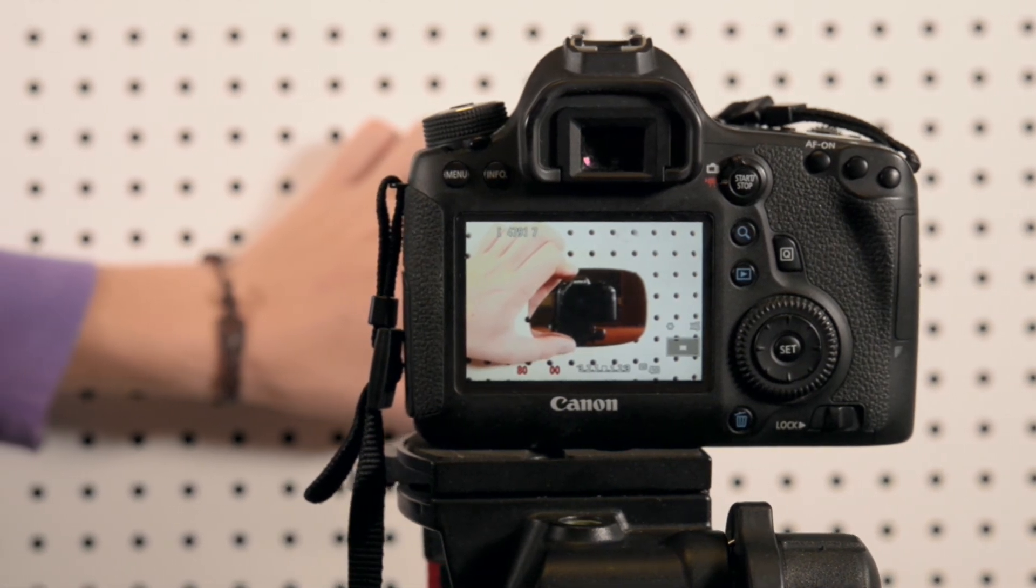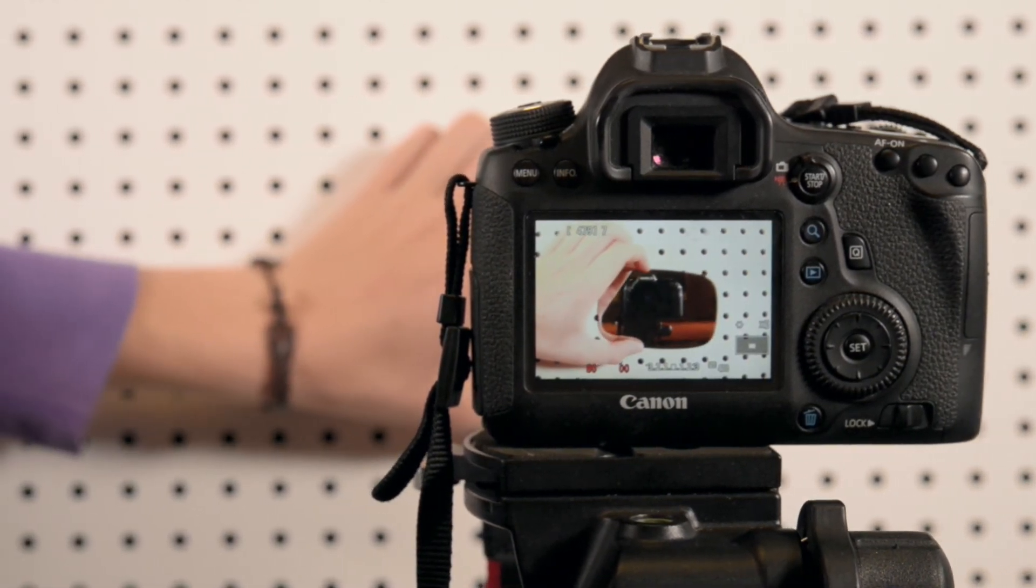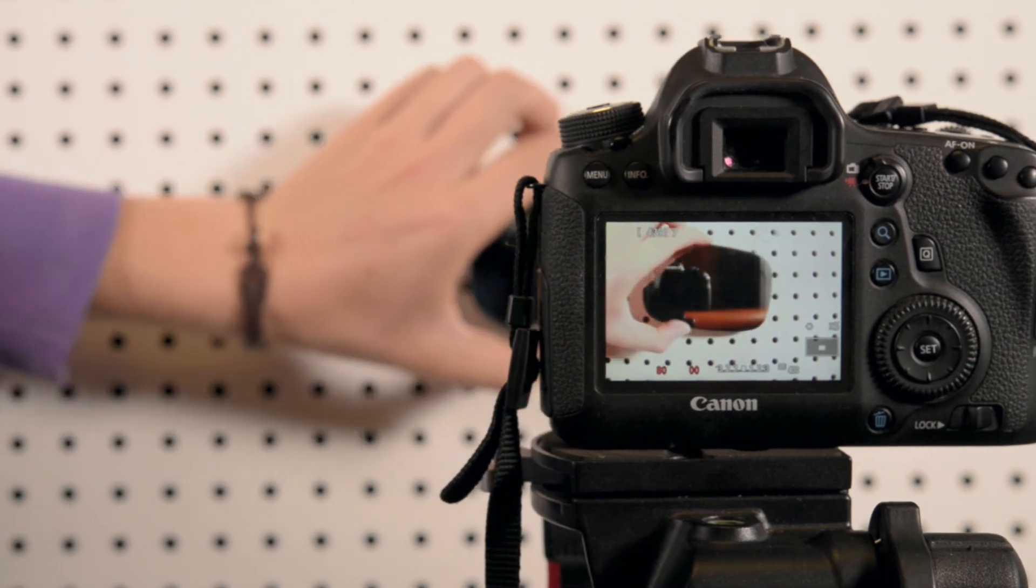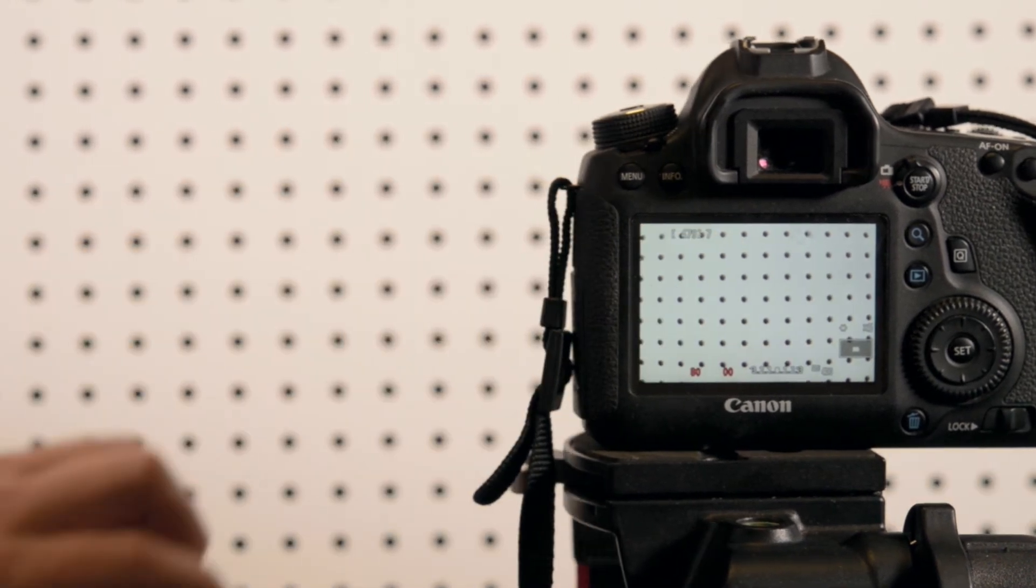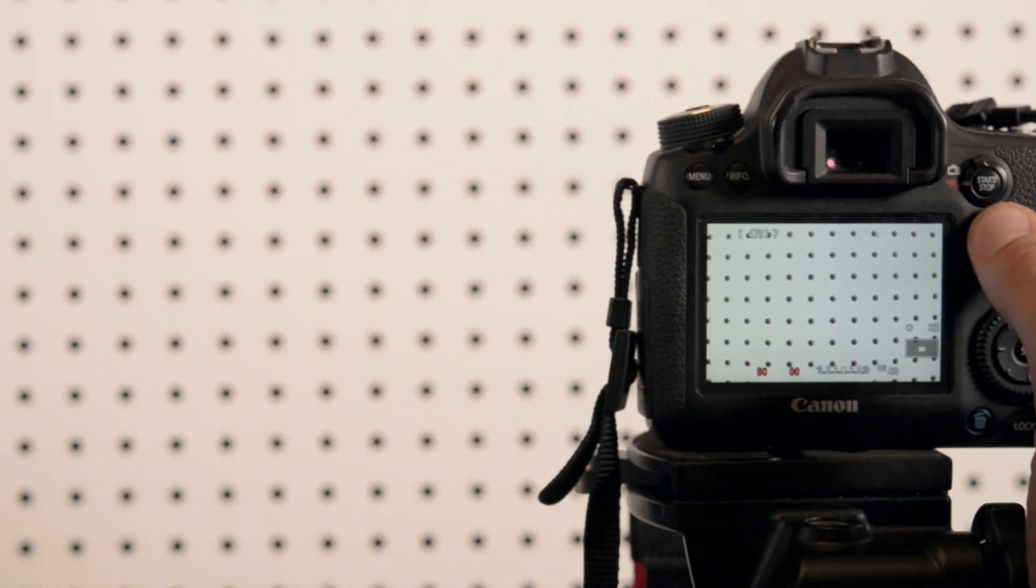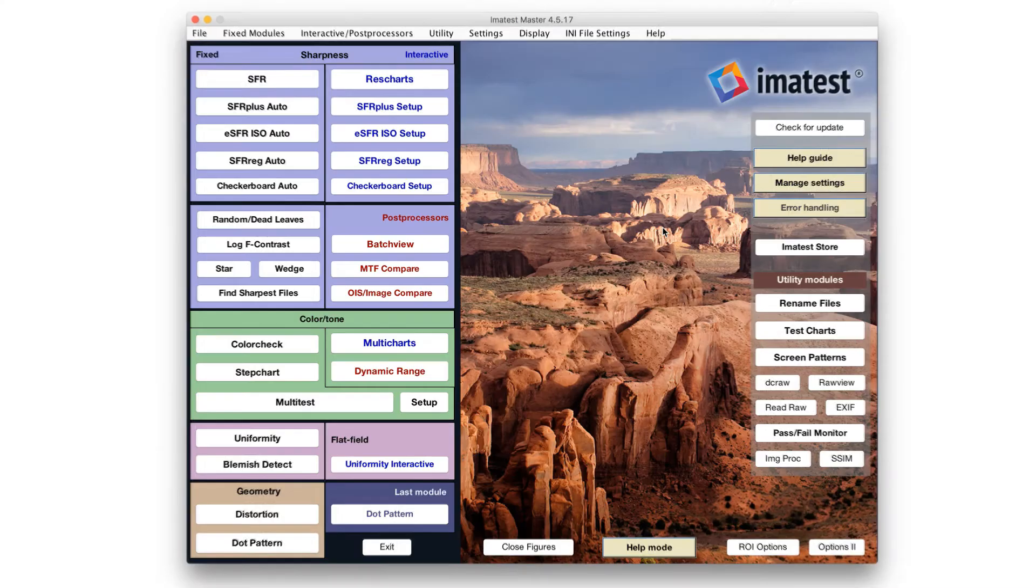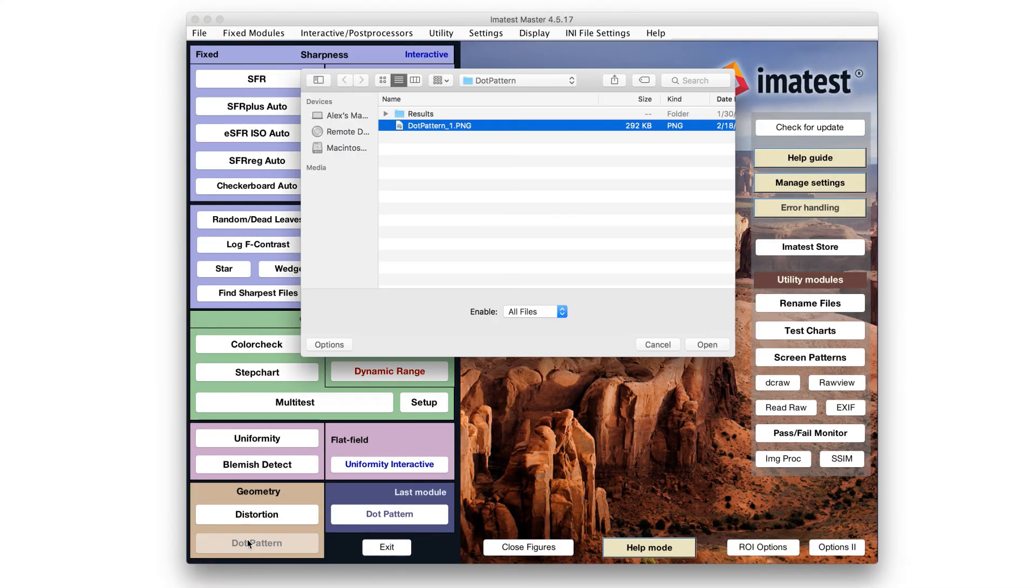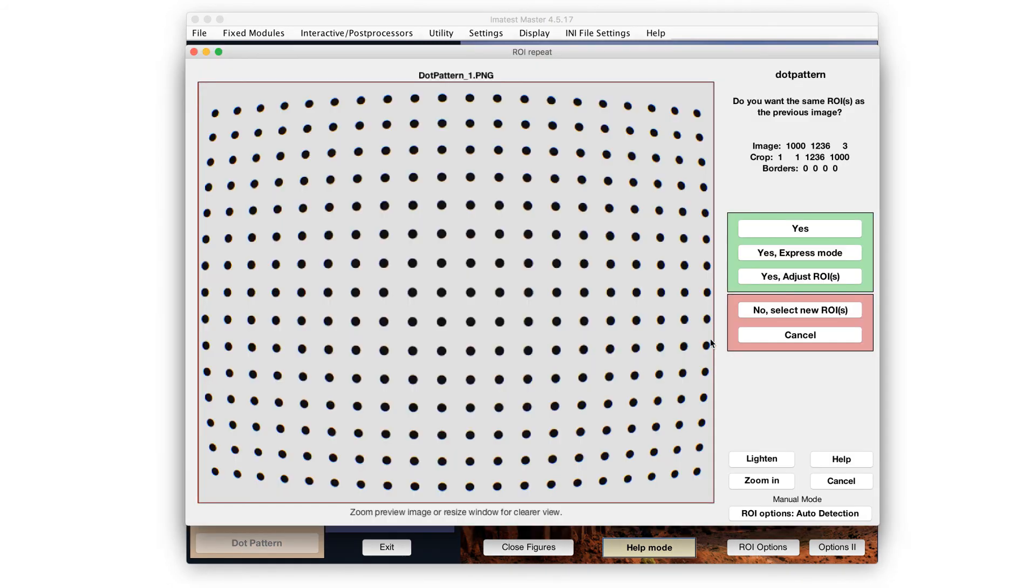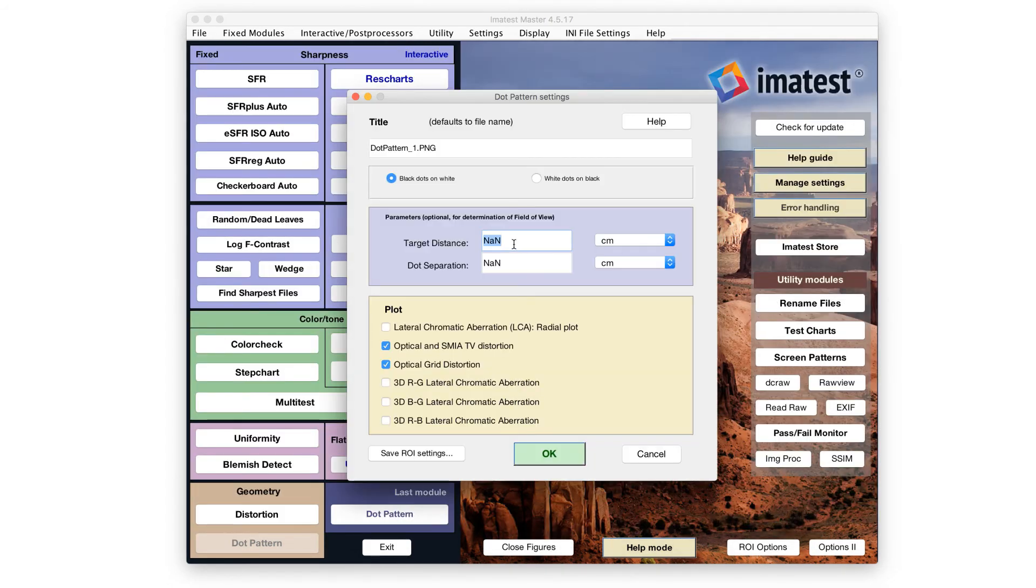Alignment can also be verified by placing a mirror parallel to the target plane. If the camera is properly aligned, the center of the lens reflection will lie directly in the center of the image. For field of view measurements, the lens to chart distance must be entered into Imatest along with a parameter that defines chart size.